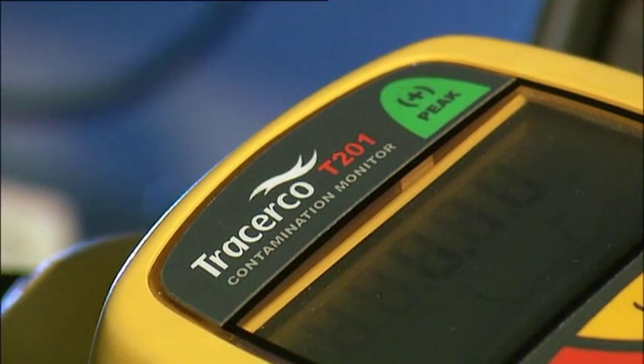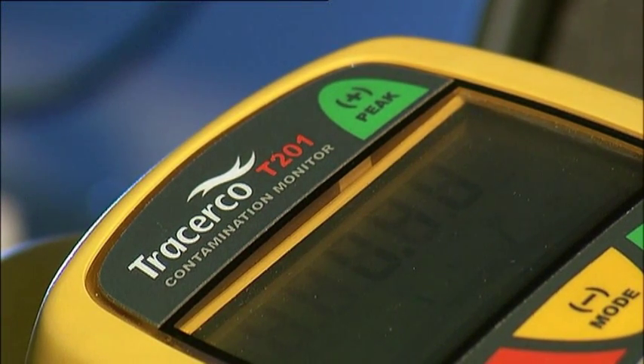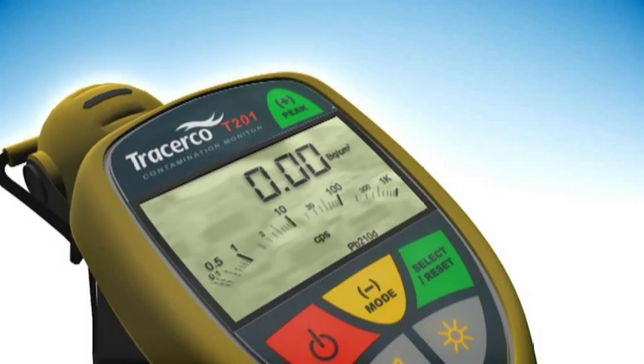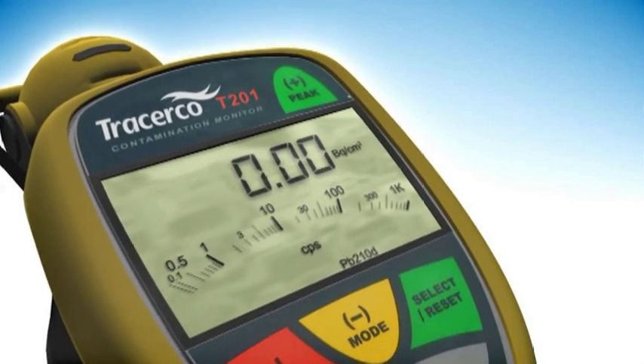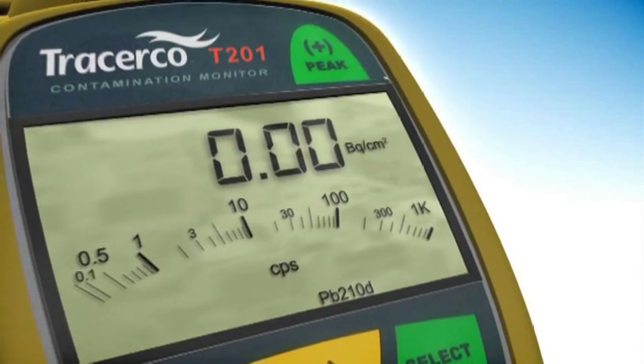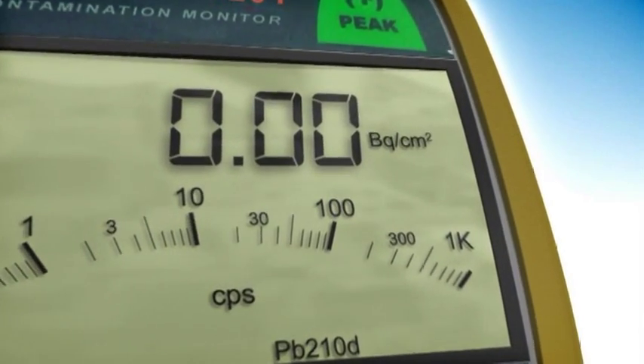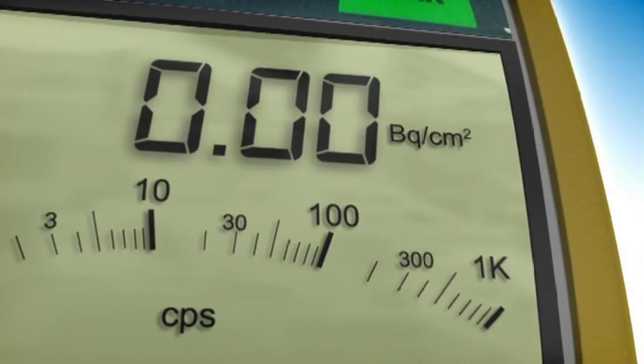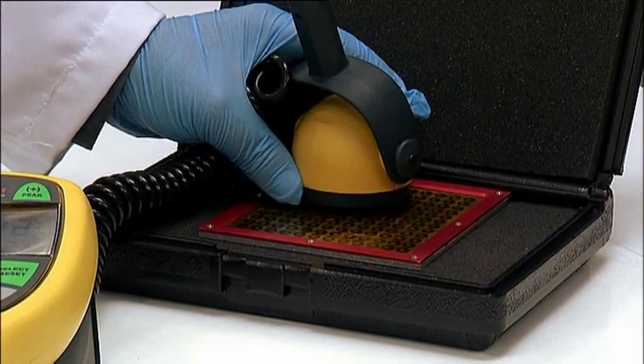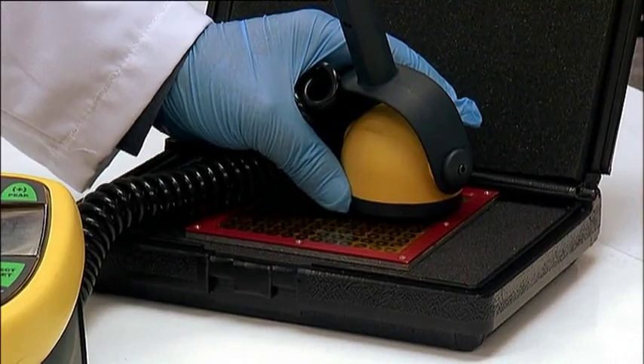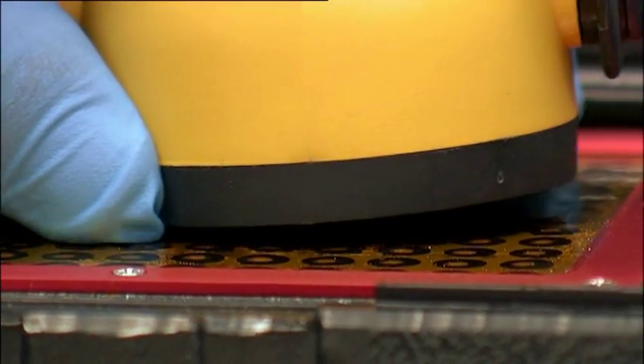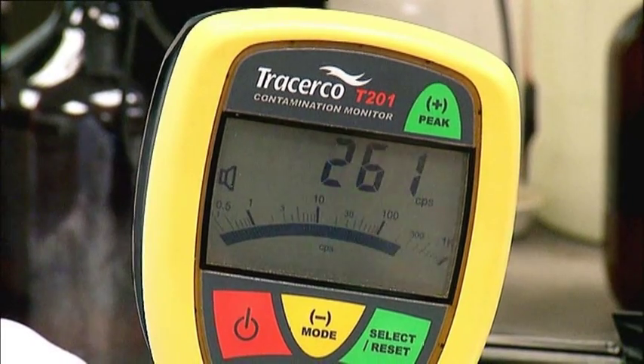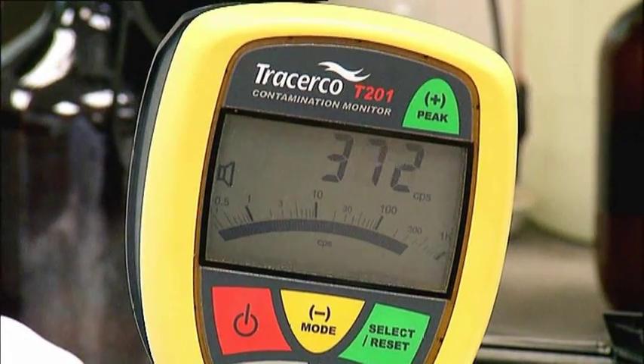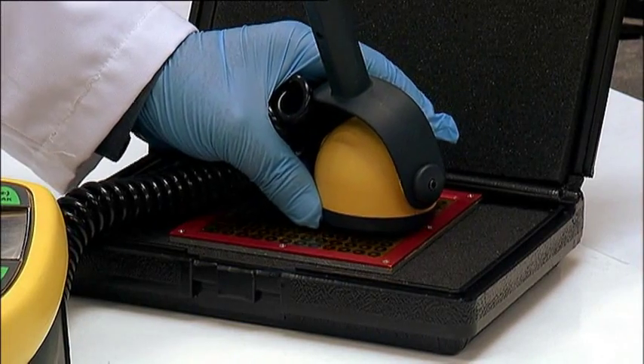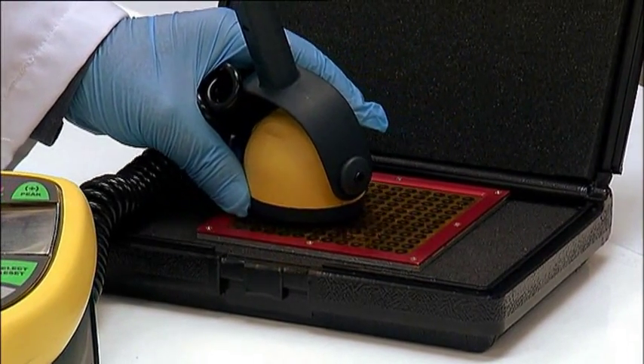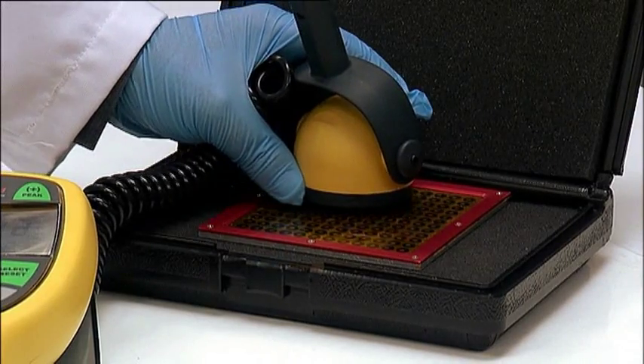The T201 monitor has been specially developed to provide a direct reading of the level of surface contamination in becquerels per centimetre squared for a number of radionuclides. These are retained in memory, which the operator may select. In order to carry out a statistically effective measurement of surface activity, it's necessary to accumulate counts over a reasonable time frame and to make appropriate corrections for the local background levels of radiation. This count should be carried out by removing the monitor detector away from any known contaminated surfaces.